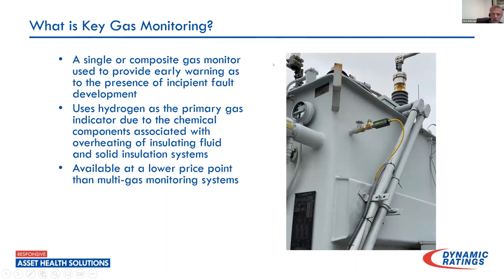With single gas monitoring, it's there to provide an early warning and we are mostly looking at hydrogen. Something I've been looking into recently is installing it in the headspace of a transformer when available, as opposed to always installing at a drain valve for oil, and just how much quicker those detection rates are. It is available at a very low price point, and it does give you a pretty good level of protection and indication that something is starting to go awry with the transformer.